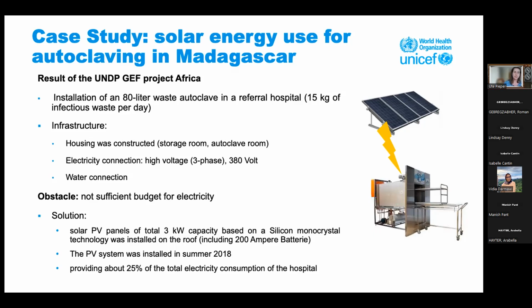There was an 80-liter waste autoclave in a referral hospital. The housing was constructed, with a 3-phase electricity connection and water connection in place. Then the health facility said they had a problem with electricity - they didn't have sufficient electricity. So the project provided solar energy with 3 kilowatt capacity, installed in 2018, and the result was that the solar panel covered 25% of the total electricity, including the autoclave, for the hospital.